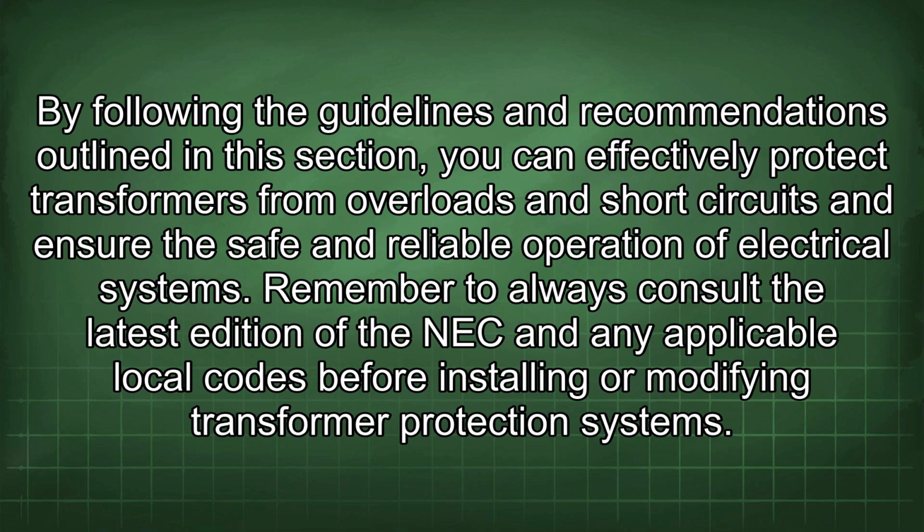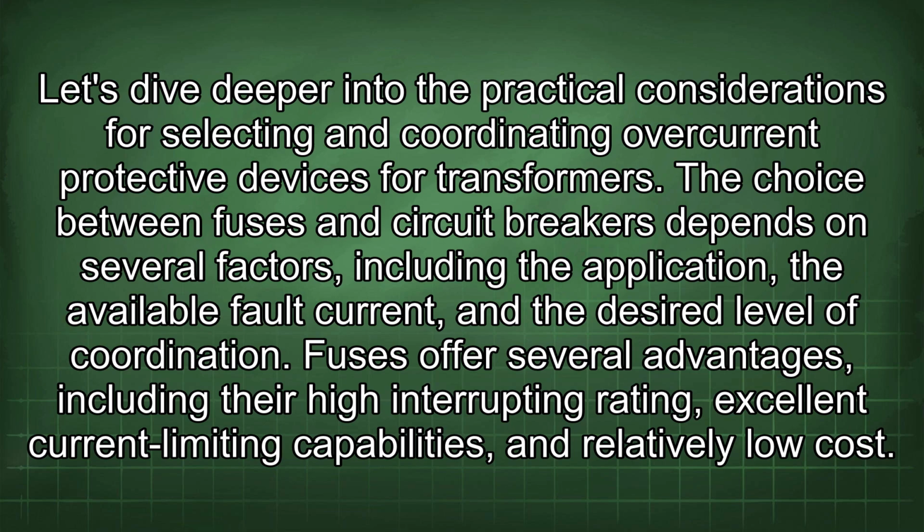Let's dive deeper into the practical considerations for selecting and coordinating overcurrent protective devices for transformers. The choice between fuses and circuit breakers depends on several factors, including the application, the available fault current, and the desired level of coordination.